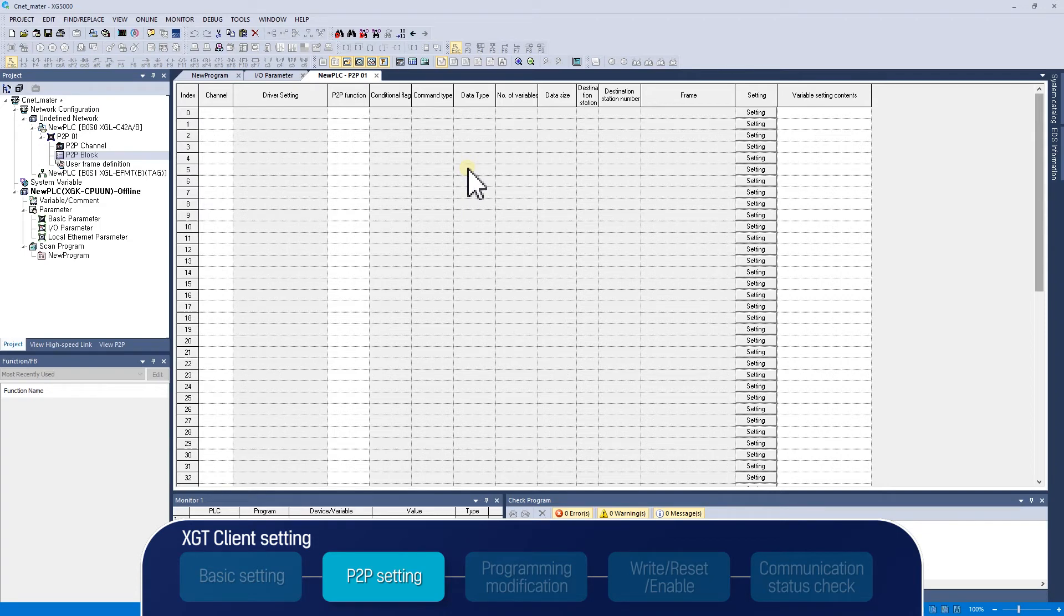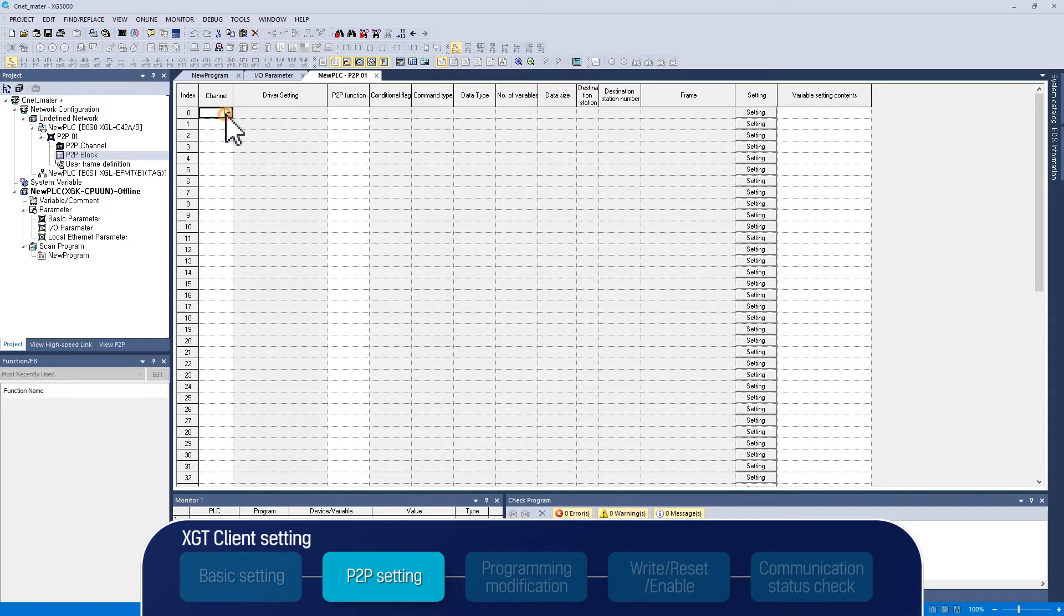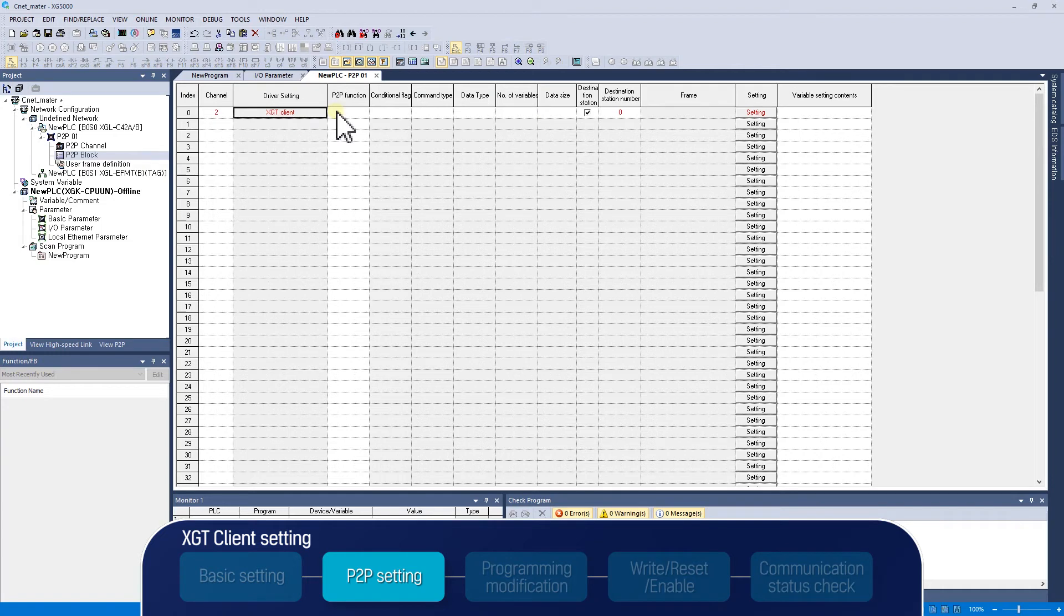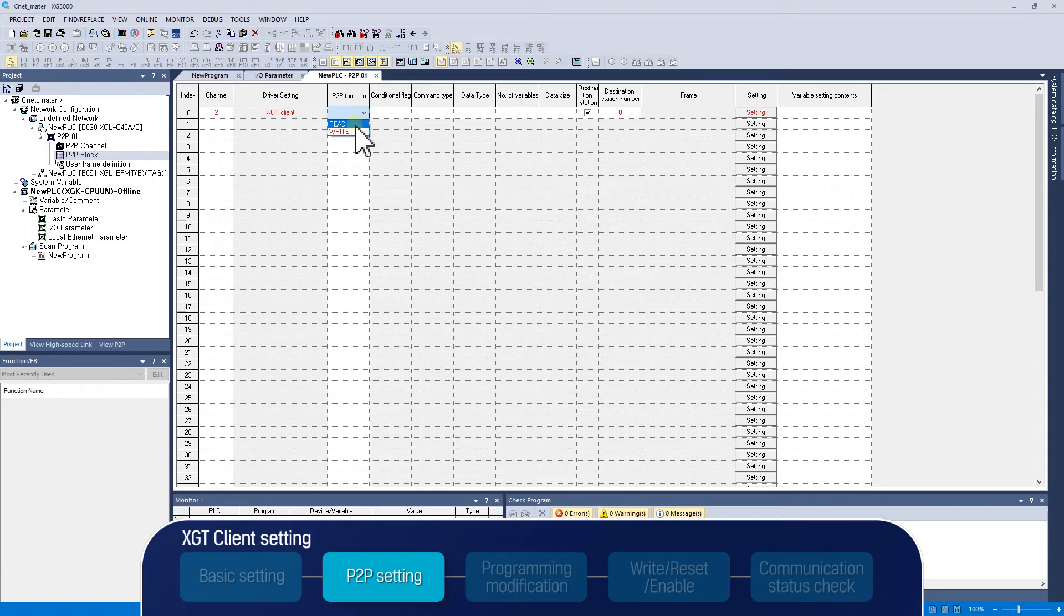When setting index 0, the first part of the P2P block, the channel, must be set up first. If the channel is set to number 2, the setting driver is loaded. The driver set here is the communication driver set in the P2P channel. Also, P2P channel, read, and write request can be selected. At index 0, the master makes a read request to the slave, so select read function.